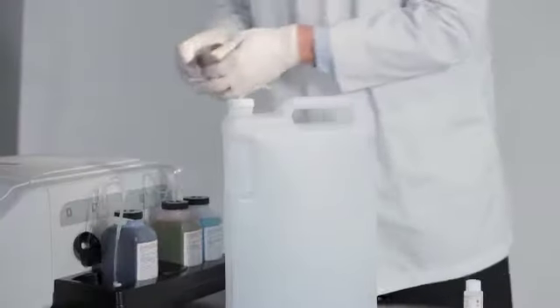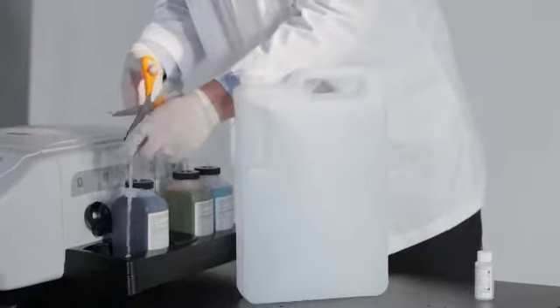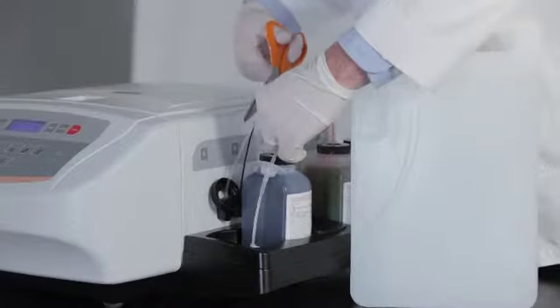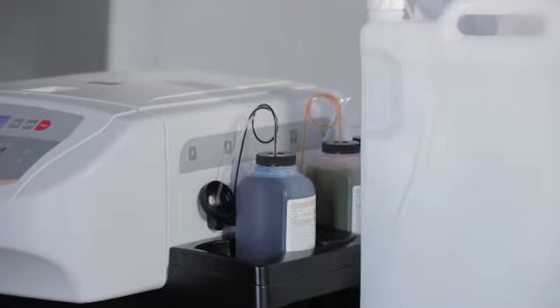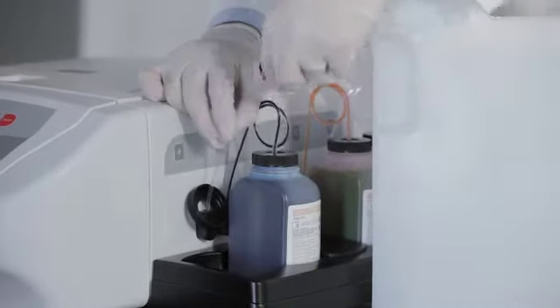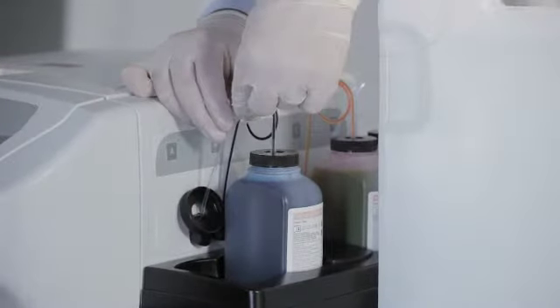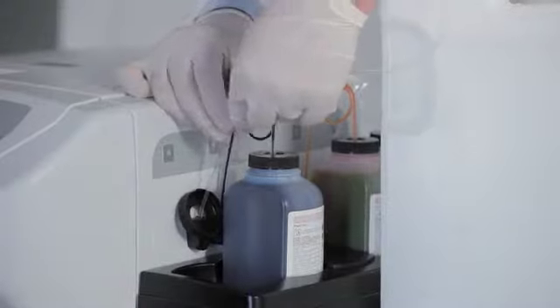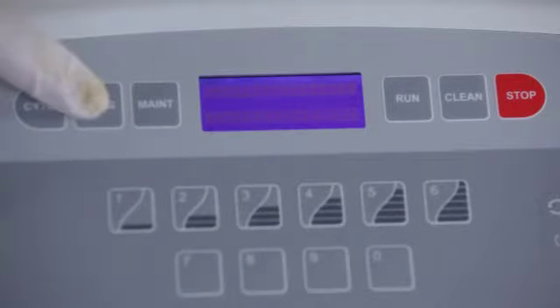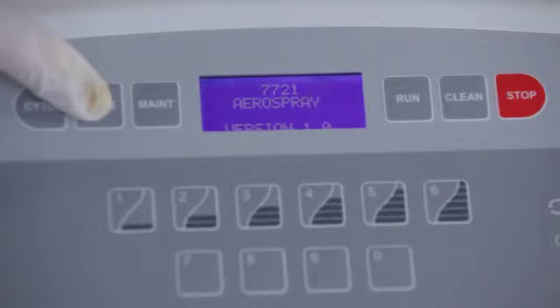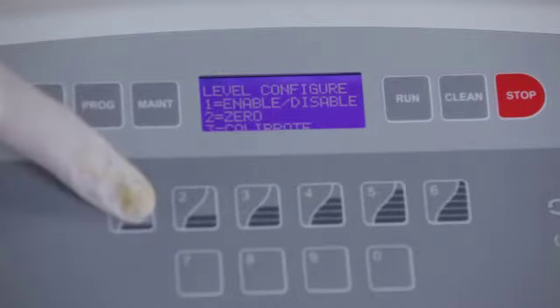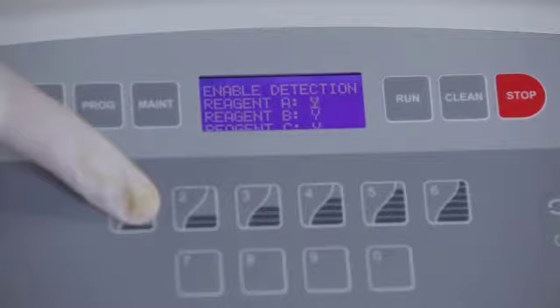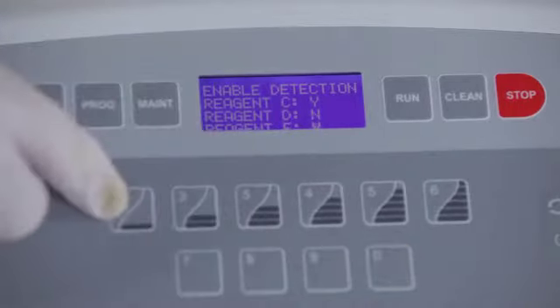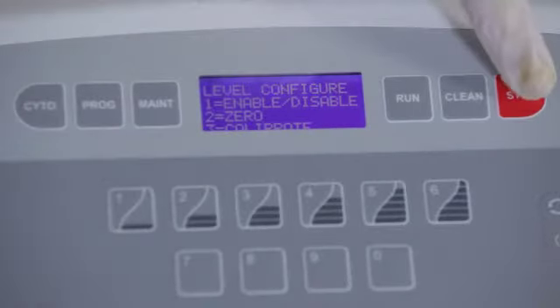A lot of water is used on the stainer, so a 5-liter container is provided with each new stainer. Connect the container by cutting the standard dip tube at its apex and then slipping the connector in the tube as it goes into the stainer. After the 5-liter container is installed, the level detection for the D line should be disabled. It is disabled by turning the stainer off, then on again. Press Program while the stainer is booting up. Press 1 for level sense, press 1 for enable disable, then press 1 for the A through C lines, and press 0 for line D. This will deactivate the level detection for the D line.